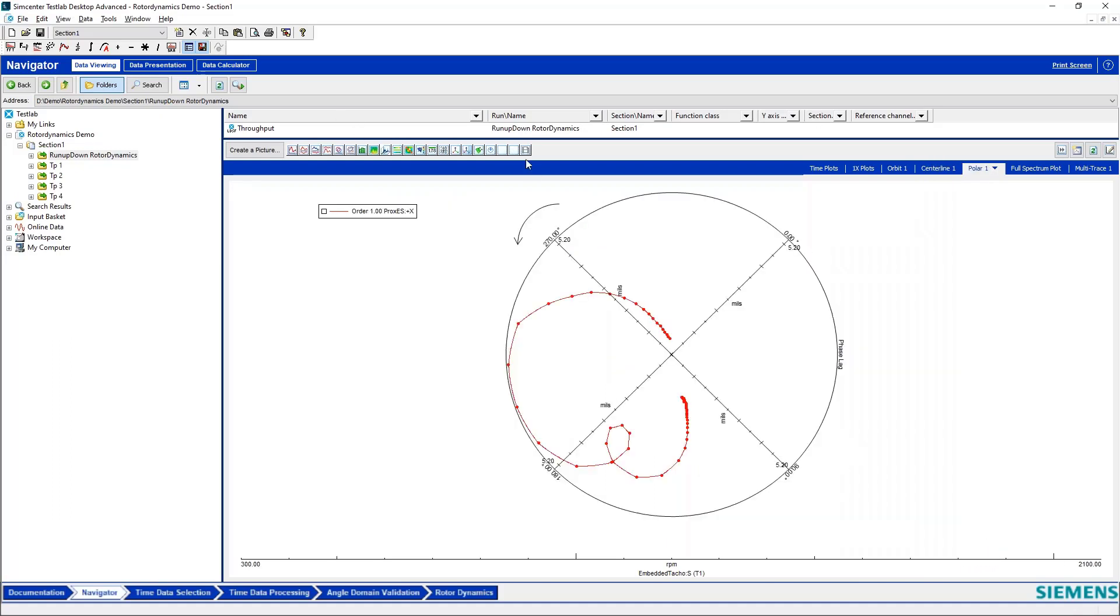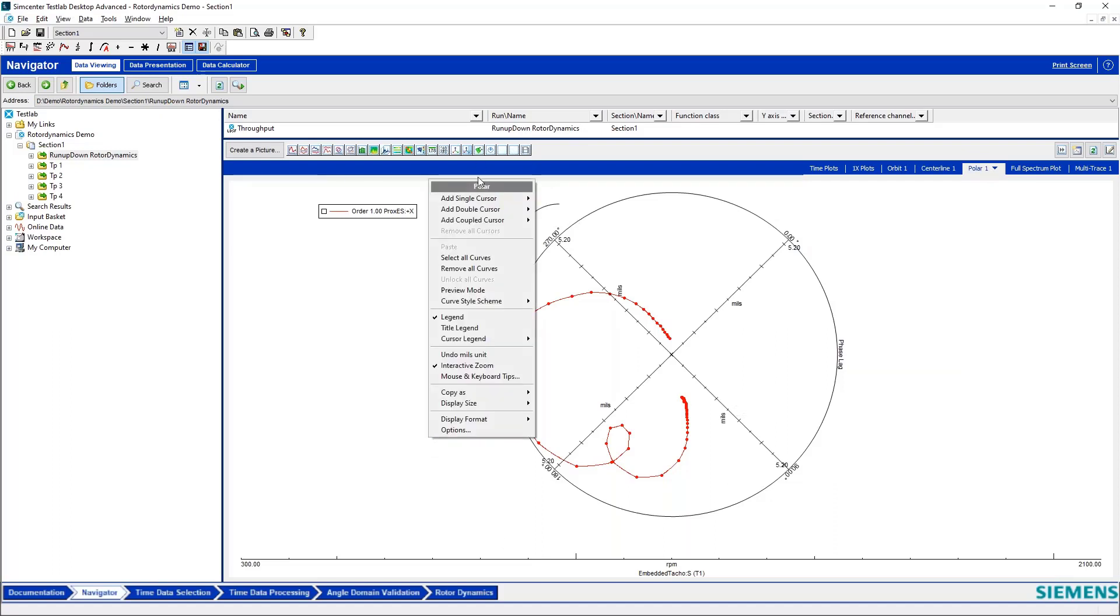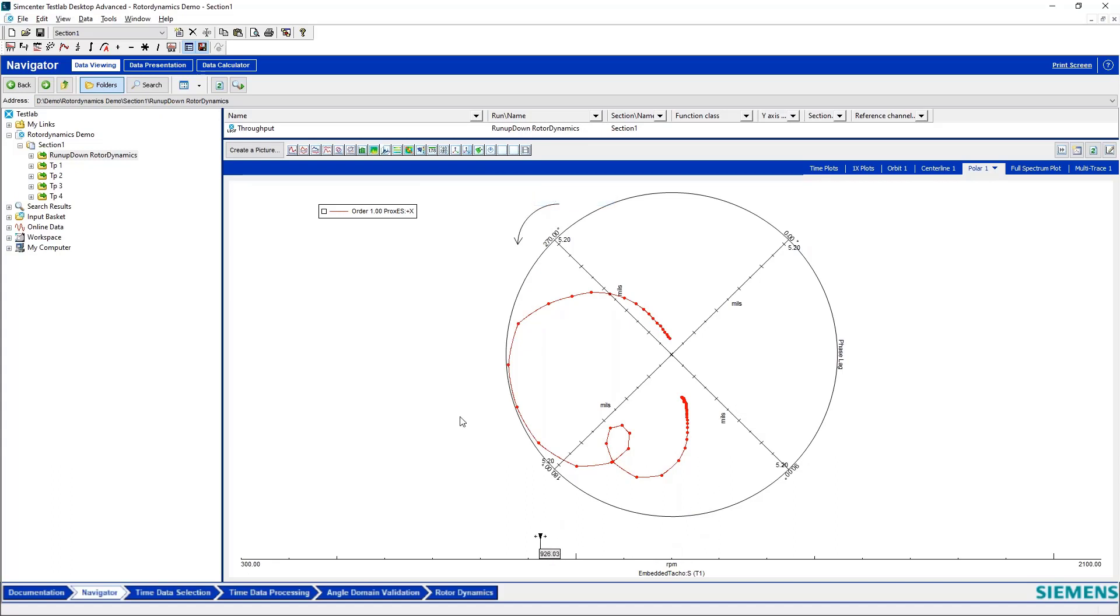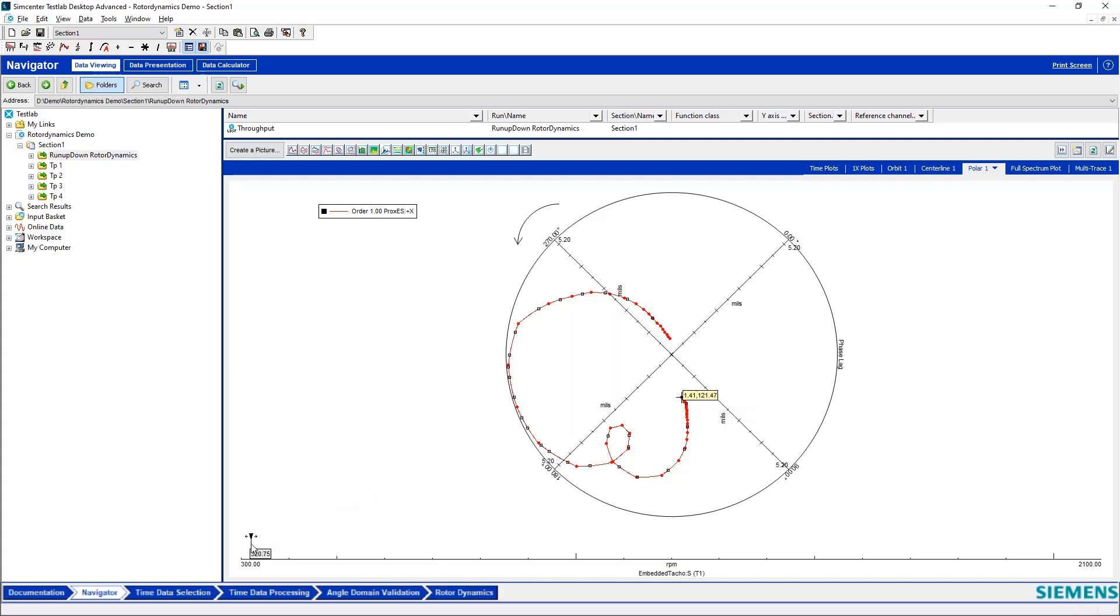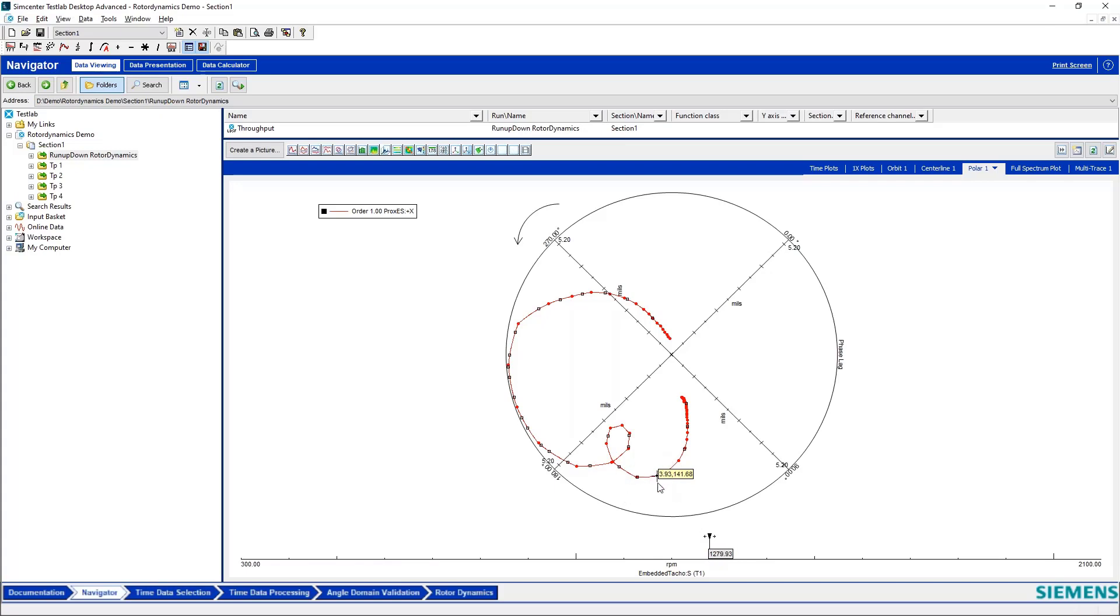I've got a polar plot that's similar to what I showed on the screen in the webinar where I can see, okay at low RPM what is the amplitude and phase of my vibration. So I see I've got 1.41 mils of vibration at a phase angle of 121.4 degrees, and I can see how that changes. And I can get to where my first resonance is suspected to be, so that's this location where I've got higher levels of vibration. And then I can move to the location of my second suspected resonance again, and I can see the phase angle and the amplitude of vibration at that location.